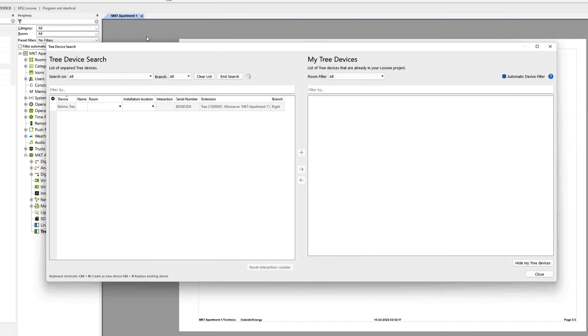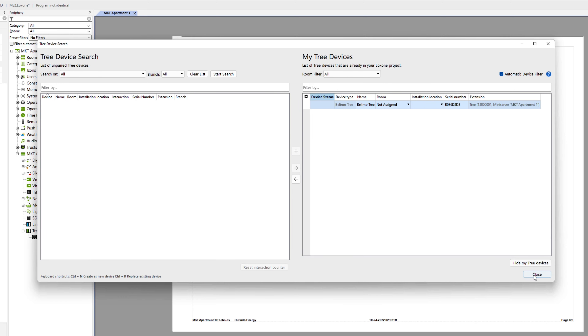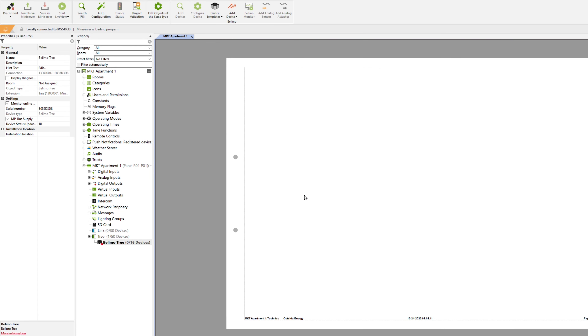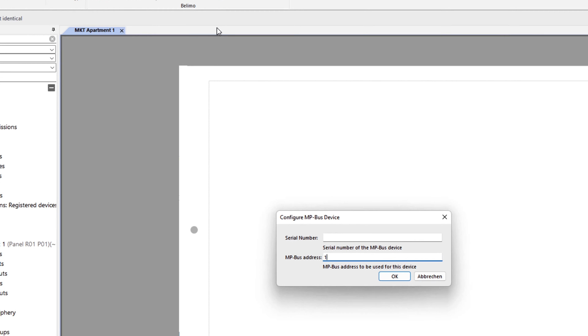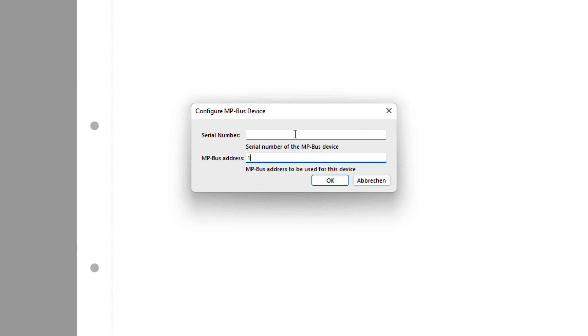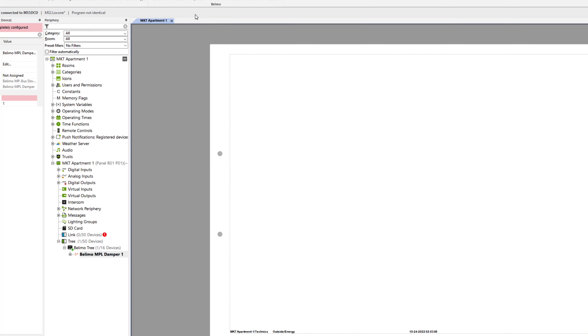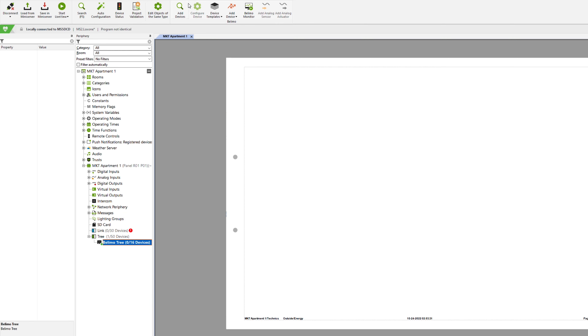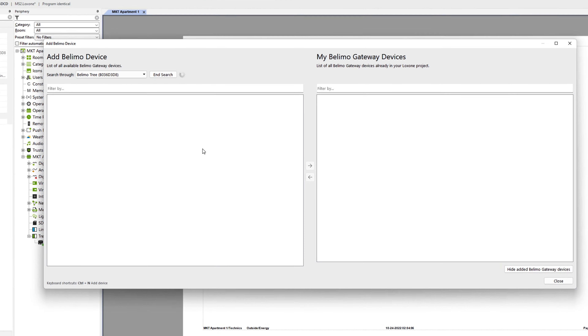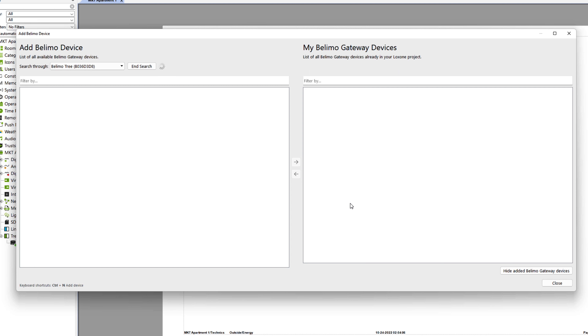Once you've added the Belimo Tree in the Loxone config, you can then add different ready-made types of supported Belimo devices. You have to enter the serial number and the MPBus address of the device. Some Belimo devices have a connect button that you can press — if the learning dialog is open in the config and you press the connect button, the device appears in the search and the serial number and MPBus address are entered automatically.